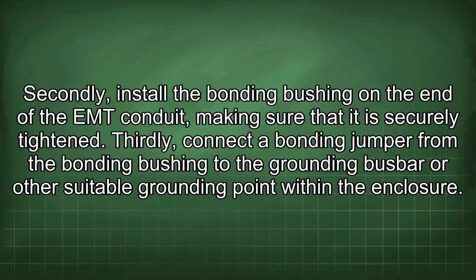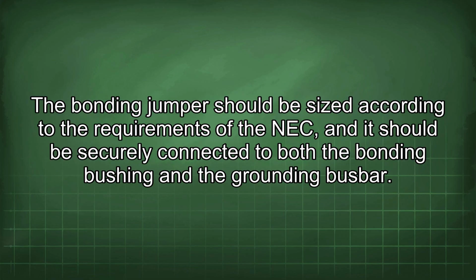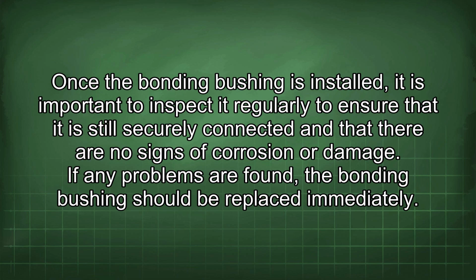Thirdly, connect a bonding jumper from the bonding bushing to the grounding busbar or other suitable grounding point within the enclosure. The bonding jumper should be sized according to the requirements of the NEC, and it should be securely connected to both the bonding bushing and the grounding busbar. Once the bonding bushing is installed, it is important to inspect it regularly to ensure that it is still securely connected and that there are no signs of corrosion or damage. If any problems are found, the bonding bushing should be replaced immediately.